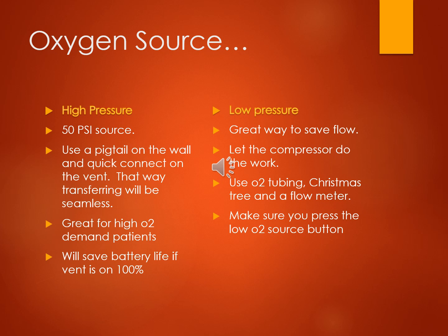Make sure that you're pressing that low O2 source so the ventilator knows that you're using a low O2 source, and it doesn't keep beeping thinking that the PSI delivery is an error, right? Because if it thinks it's not getting 50 psi, it's going to start screaming at you, and you'll know right away. That 50 psi source is that quick connect that you have into the wall. Most of them are Ohmedas or Chemetrons that are the source on the wall. You can put one on even the newer tanks that they have, the handle tanks that we call them.